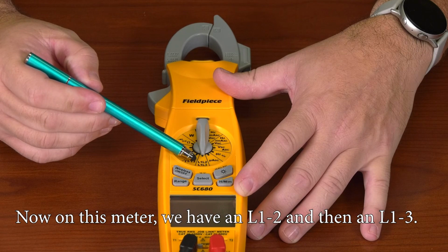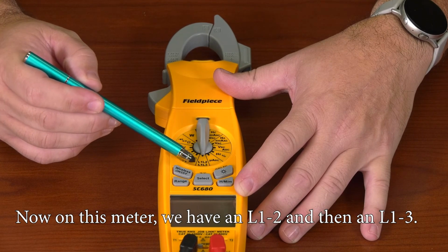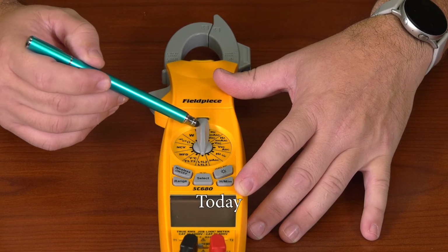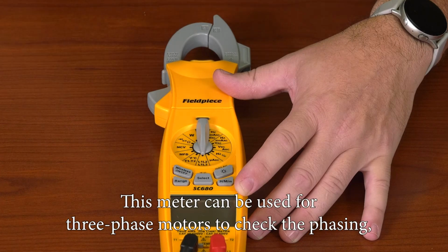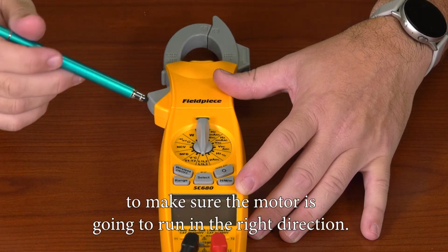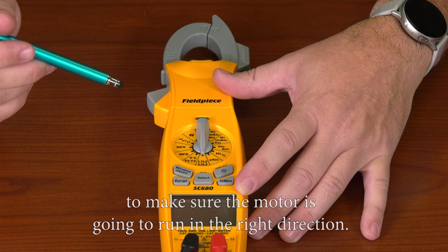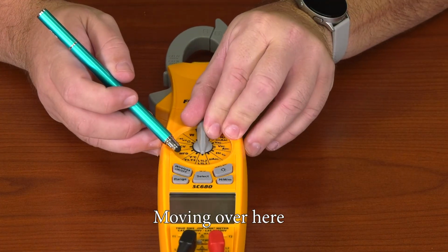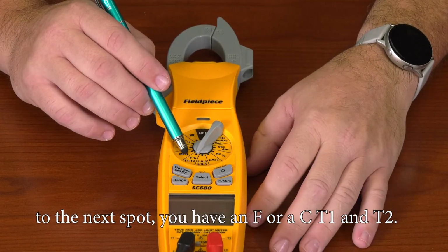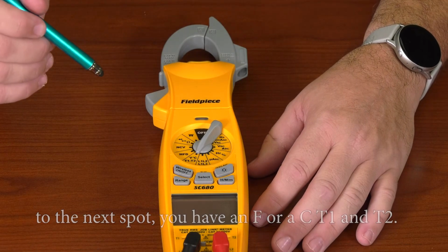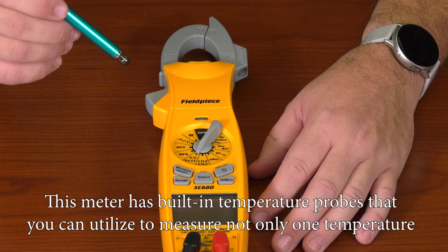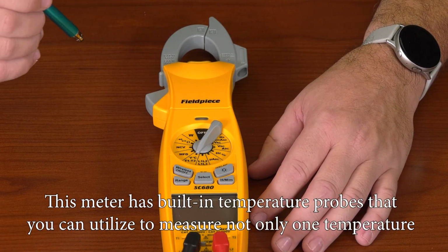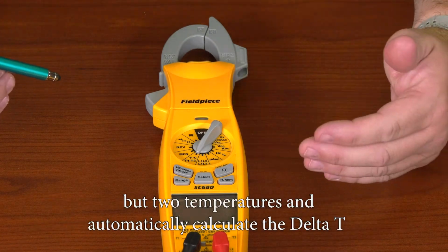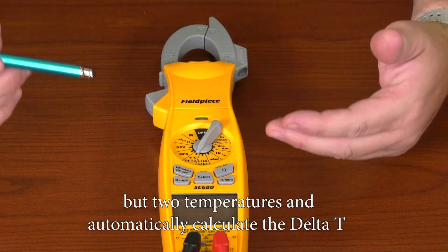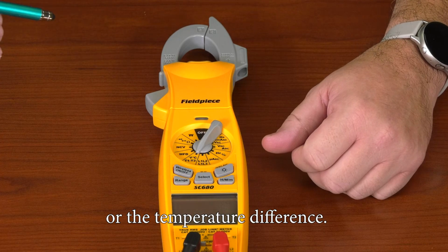Now on this meter, we have an L1, 2, and then an L1, 3. This meter can be used for 3-phase motors to check the phasing to make sure the motor is going to run in the right direction. Moving over here to the next spot, you have an F or a C, T1 and T2. This meter has built-in temperature probes that you can utilize to measure not only one temperature, but 2 temperatures and automatically calculate the delta T or the temperature difference.